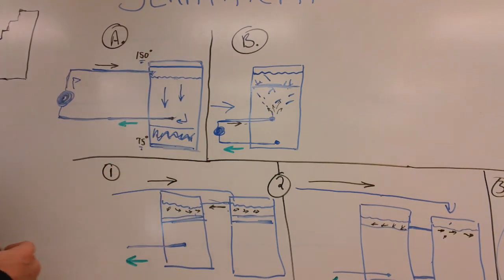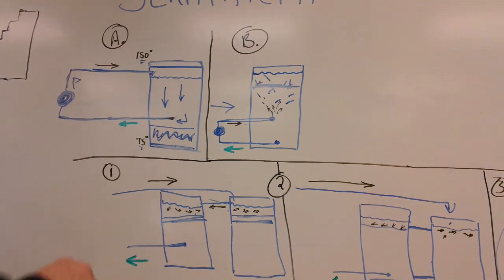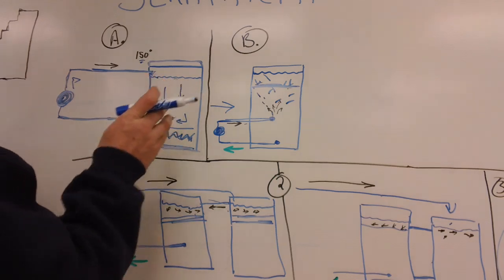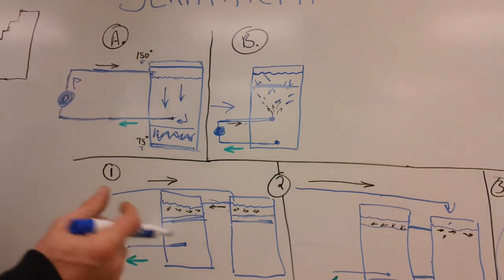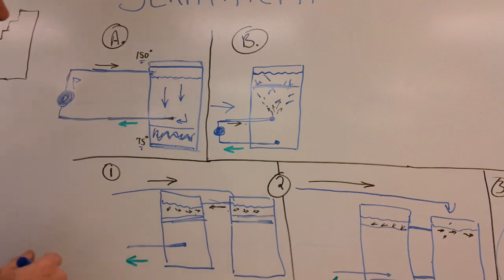What I ended up with was 72 to 75 degree water on bottom here and this area here, and 150 degree water up on top, which obviously is not too much homogenization and I'm not heating up all of my water, so I'm probably not storing the BTUs that I could be storing.